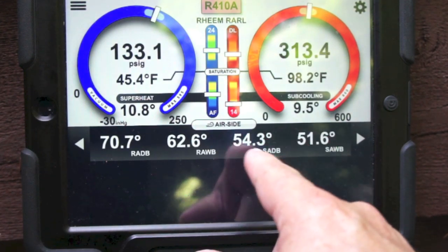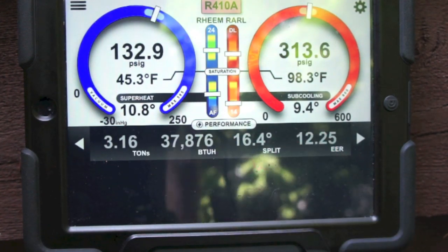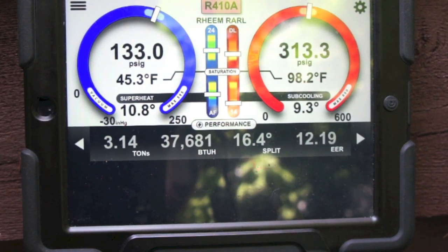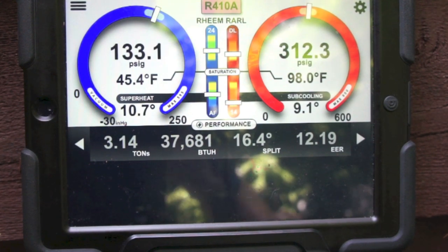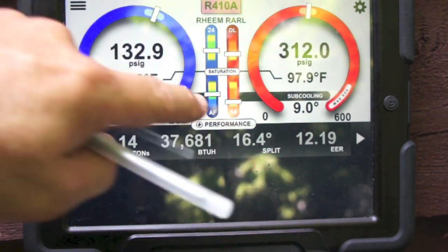Alright, so now if we scroll through here, we can see our EER is 12.25. We're running 37,800 BTUs, 3.16 tons of cooling, a 16.4 degree split. Split is dead center, where it should be, in the center for airflow.